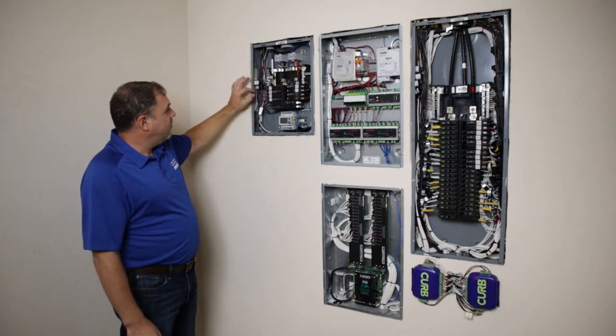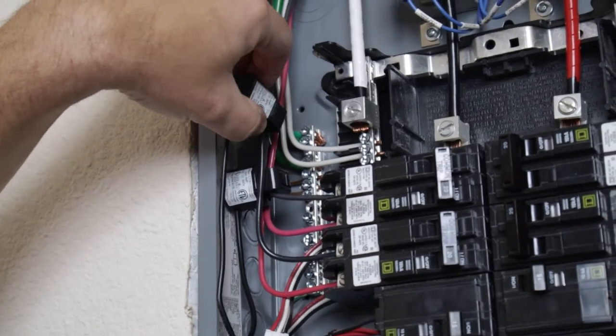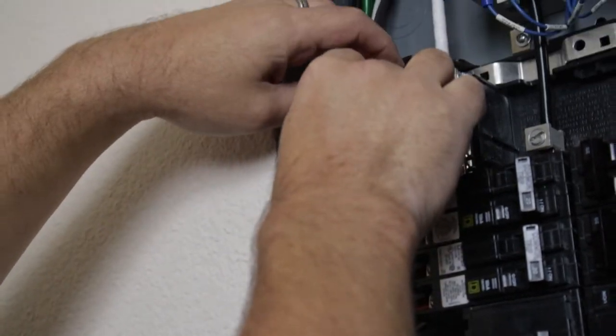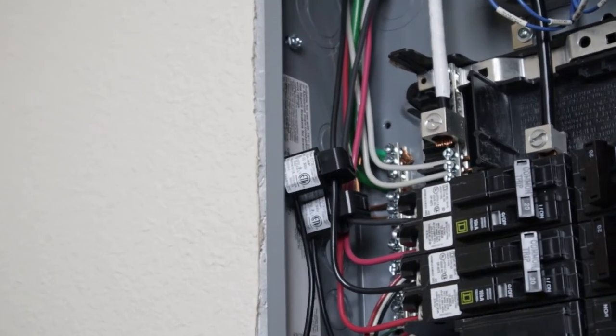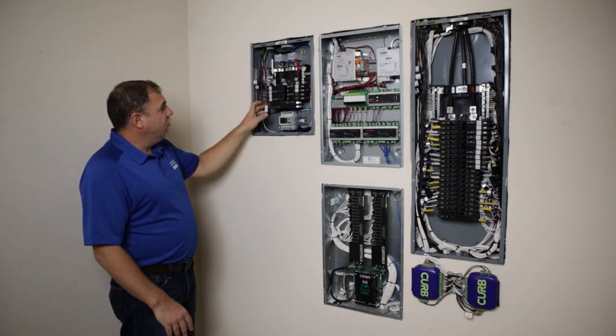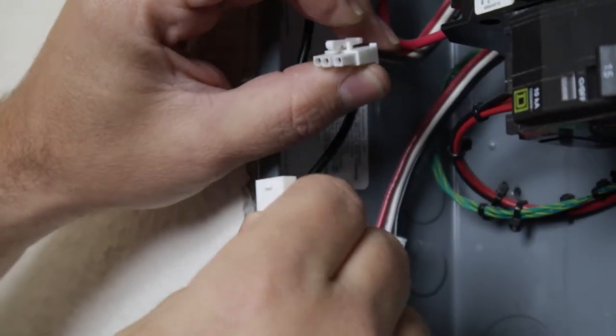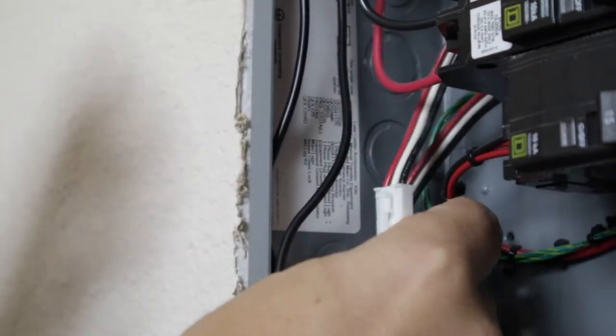These are controllable breakers connected to our Adapt Energy panel. This wire connected to the breaker has a little box called a current transformer — its job is to read the power the solar is producing coming into the circuit breaker. I have one on each circuit breaker so I can monitor each solar array string individually. Not only can I monitor, I can also control each array.